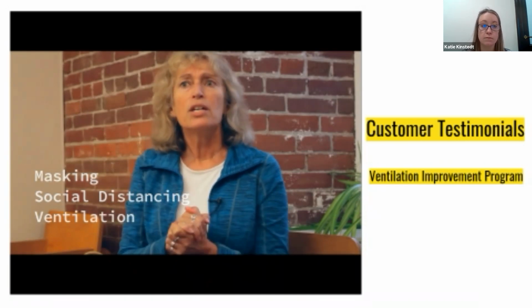So if a building does have ventilation, like CVOEO, they have air handling units that are already bringing in fresh air, and they are mixing that fresh air with building air. The two things we need to do with those systems is calculate how much ventilation air the building needs based on the occupancy level, and then that it's filtered.